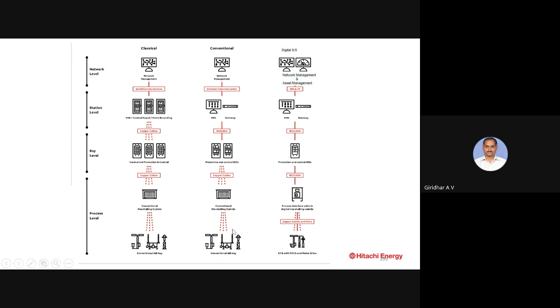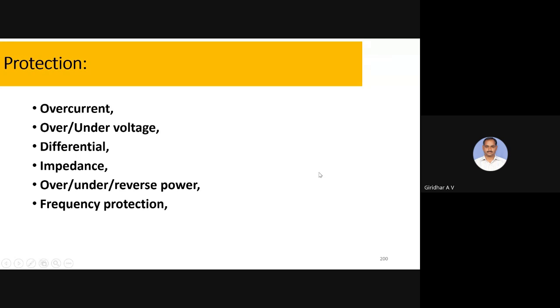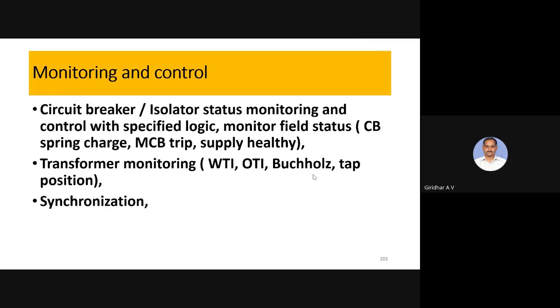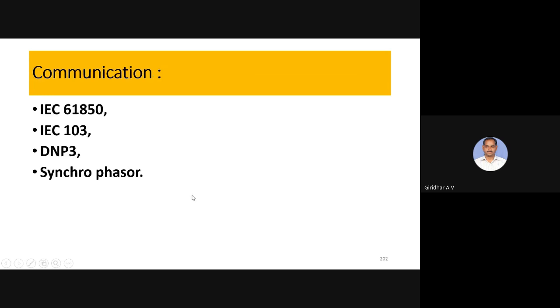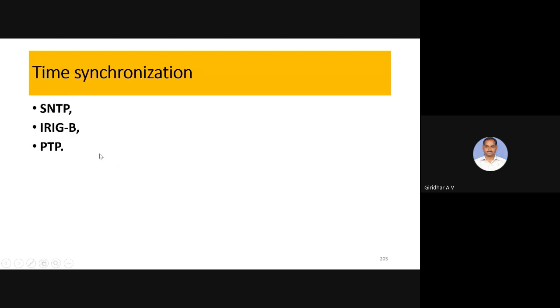So you can see the different layers, even optical fibers and all they are using, so that effectively, without noise, you are going to take appropriate actions also. So through these IEDs, you are going to get overcurrent, under voltage, differential protections. Even circuit breaker isolator status monitoring, everything can be done. So these are the different communications it can do: through the process bus communications, IEC 103 and DNP3 protocols, synchrophasor measurement, PMU measurements. Features also will be added in these IEDs. Time synchronization, these are the different ways they are using.